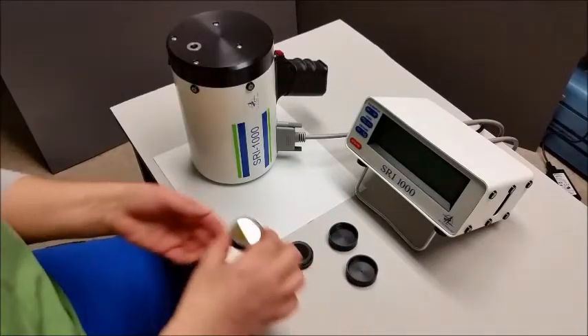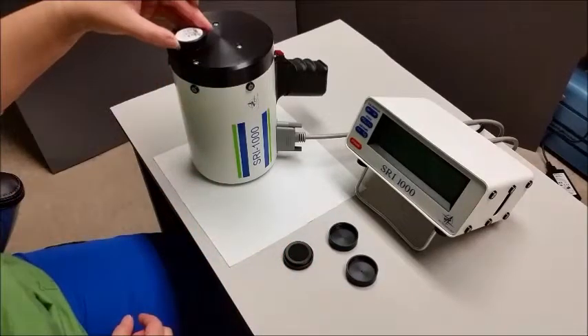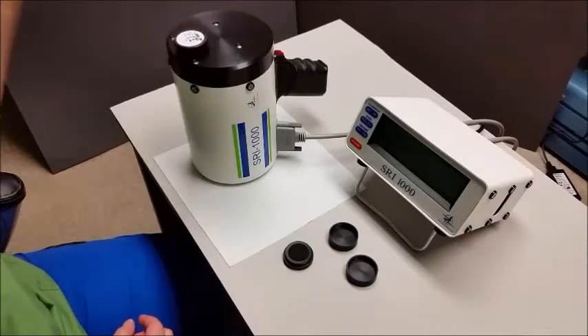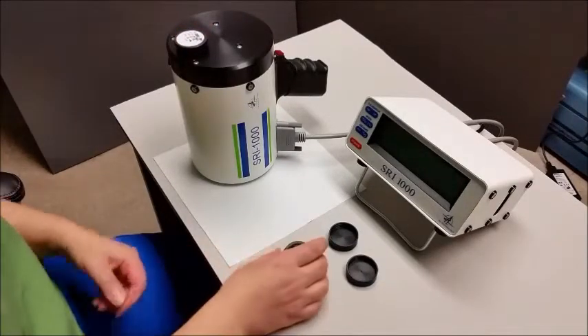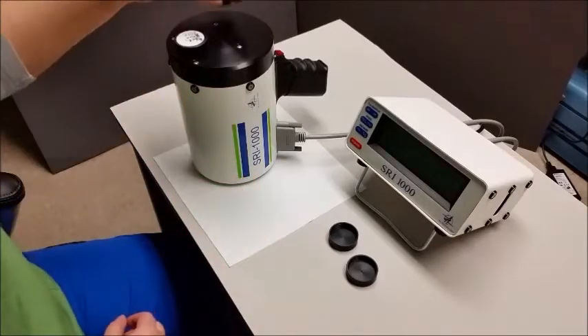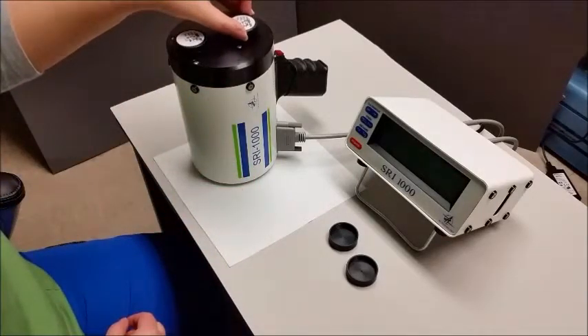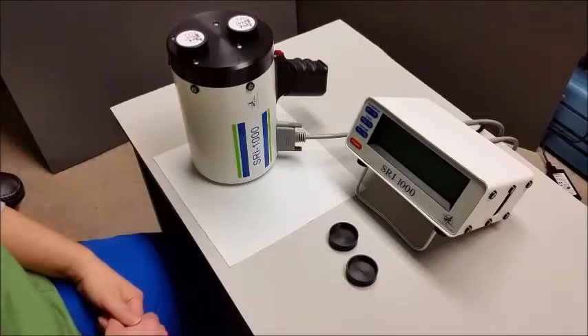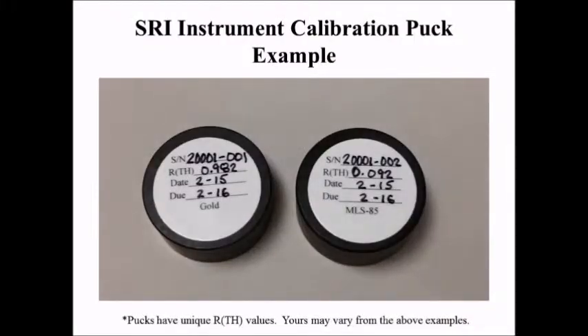Step 2. Place the gold sample gold side down, centered on the measurement port. Carefully place the black sample black side down, elsewhere on the measurement head. Step 3. Allow 1 minute for the surface of the calibration samples to reach the same temperature as the measurement head. Step 4. Each of these calibration samples has an RTH value, total hemispherical, written on its label. For obtaining total hemispherical thermal emittance, use this value in the following instructions.